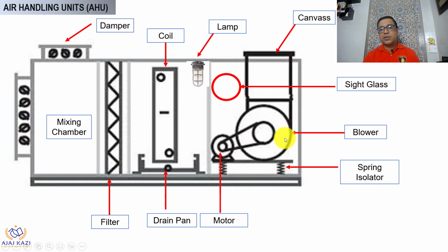Then we have the motor and blower assembly. At the end of the blower there is also canvas, because the blower's vibration should not get transferred to the duct, and that's why there is a canvas. Now the blower, again, to reduce the vibration level, also has a spring isolator over here.